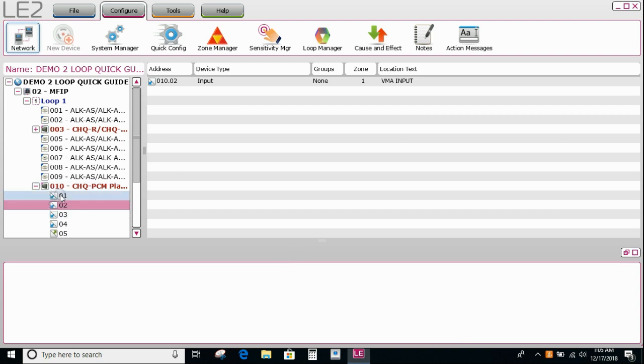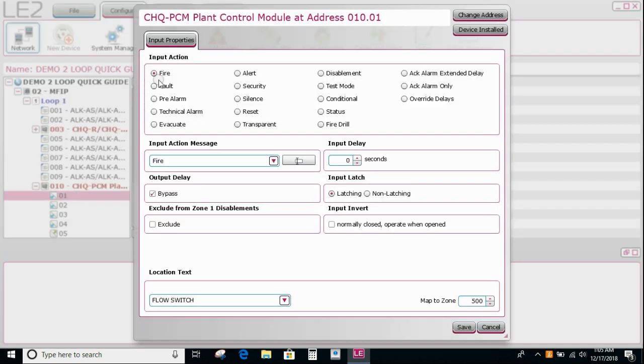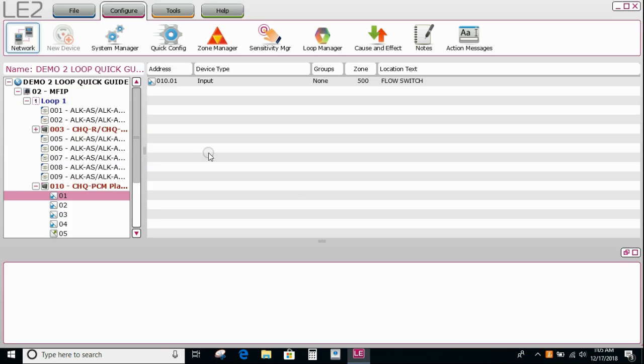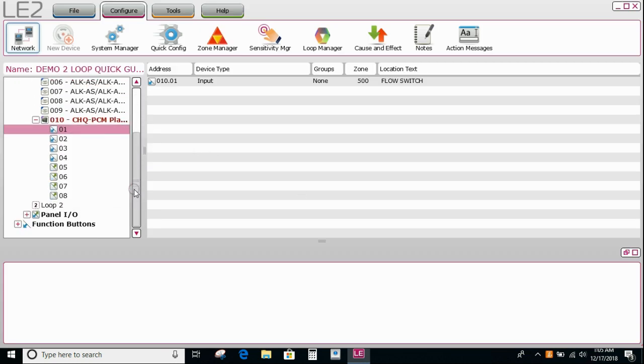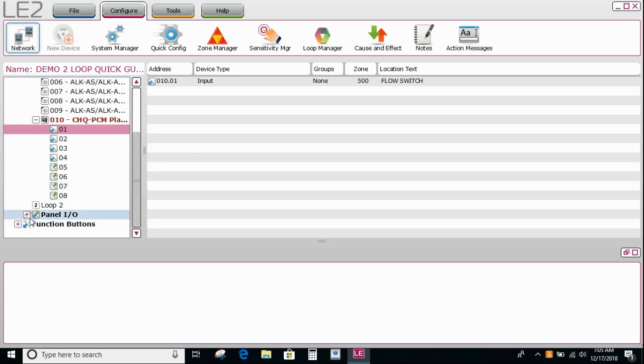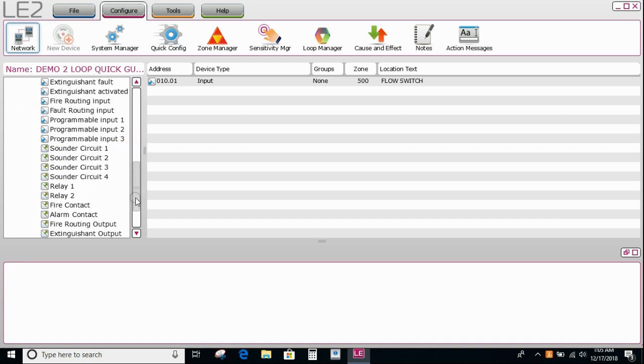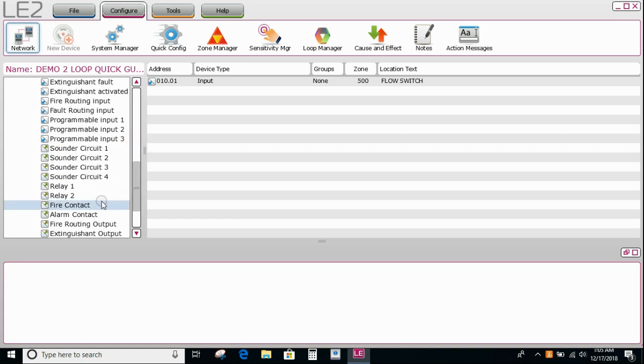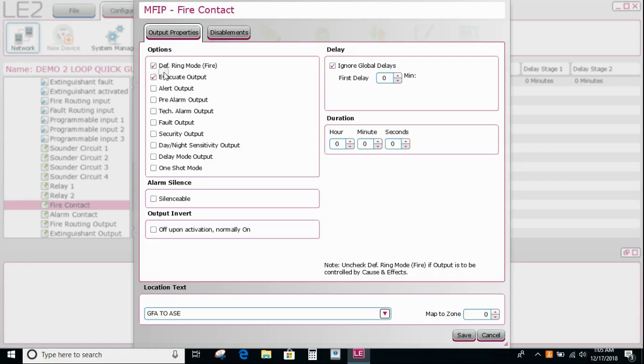So if you remember correctly, we set up the fire one as a fire condition. So it has the input action of fire. So I'm going to set up now my relay that goes to my brigade for fire, which is if you remember right, the fire contact. And by default it had the default ring mode tick. So this output will operate by any input, no matter what the input is, if it has been selected as a fire type input, which our flow switch has been. So that's already done.